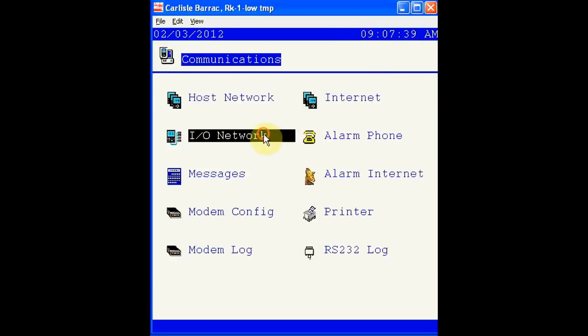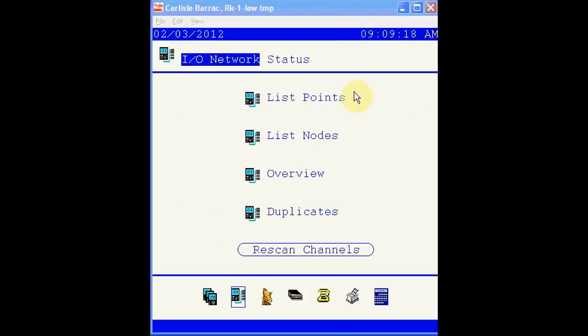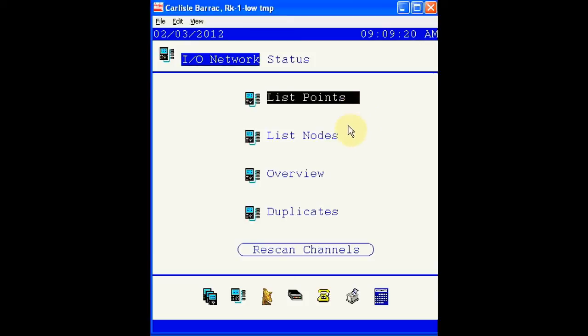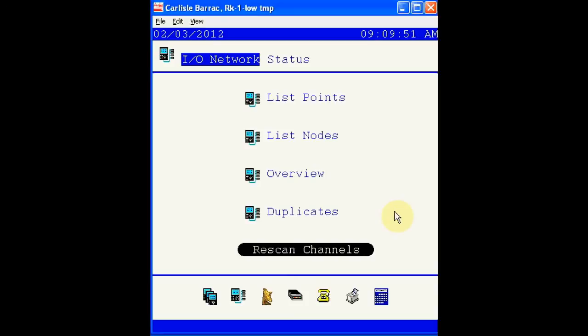Next, the I/O network. List points is used to list points assigned. List nodes will list all the boards assigned and their status. Overview will give us more details about individual boards, including AK2 communication modules. And duplicates will list any duplicate nodes on the network. This is typically used during commissioning and installation. Rescan channels gives us the option to reestablish communication to existing boards or bring new boards online with the AK2-55.